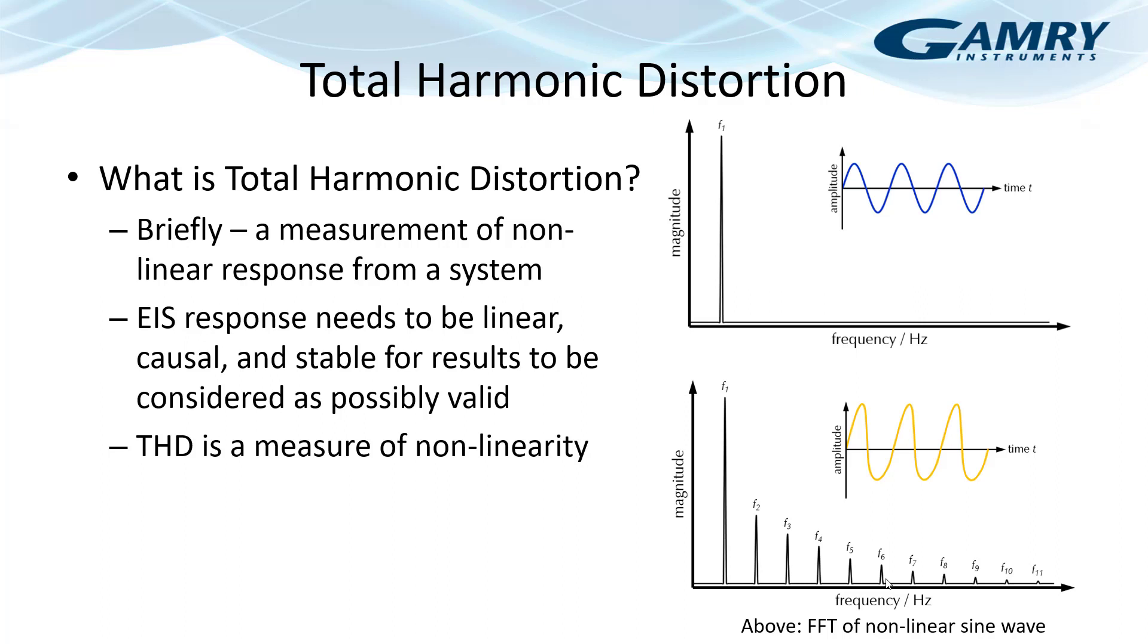So let's go over what total harmonic distortion is, and obviously within this short video I can't get through everything, but we do have a very good application note on our website that explains this in more detail, or of course you can go to the literature to figure out what this is. But briefly, total harmonic distortion is a measurement of non-linear response from a system. So this would be from your cell. I'm going to assume you know something about EIS. You should know that EIS response needs to be linear, causal, and stable for the results to be considered as possibly valid. If any one of those three fails, then your data are not valid for quantitative purposes. And so THD helps us identify this non-linearity.